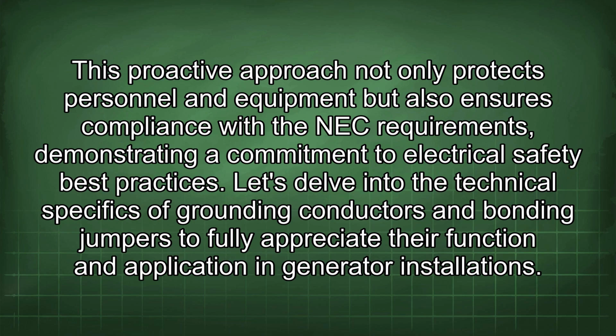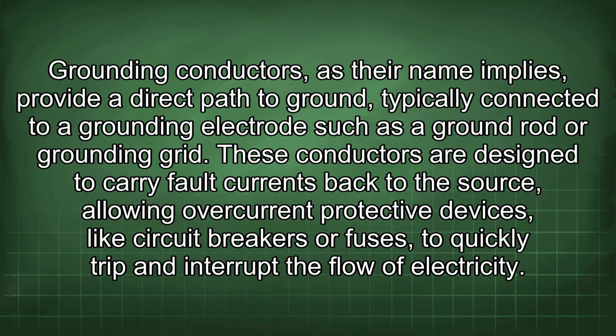Let's delve into the technical specifics of grounding conductors and bonding jumpers to fully appreciate their function and application in generator installations. Grounding conductors, as their name implies, provide a direct path to ground, typically connected to a grounding electrode such as a ground rod or grounding grid. These conductors are designed to carry fault currents back to the source, allowing overcurrent protective devices, like circuit breakers or fuses, to quickly trip and interrupt the flow of electricity.